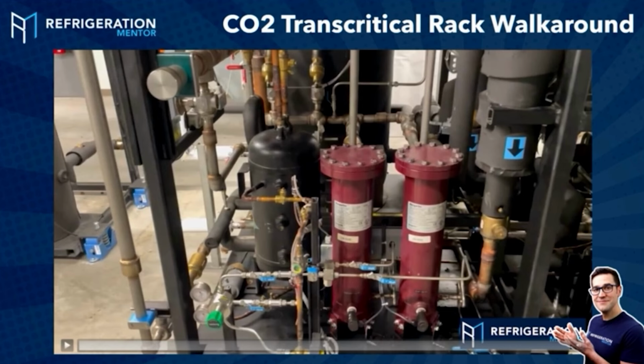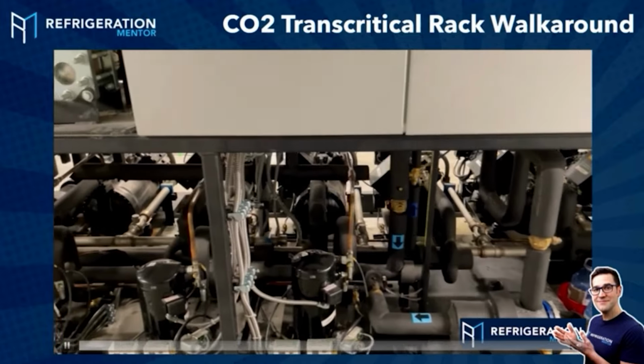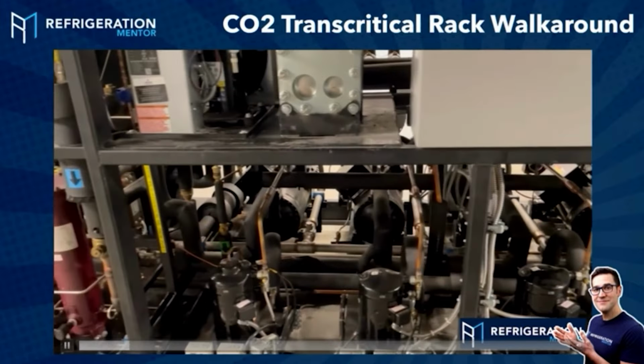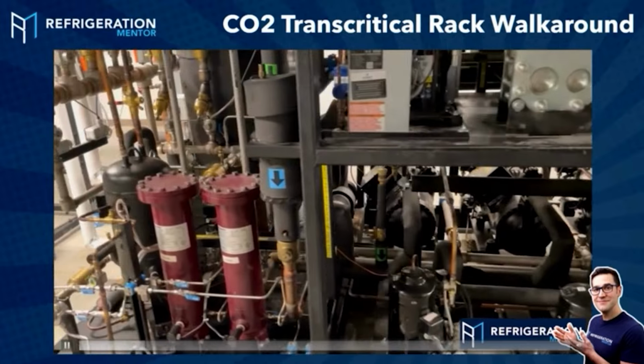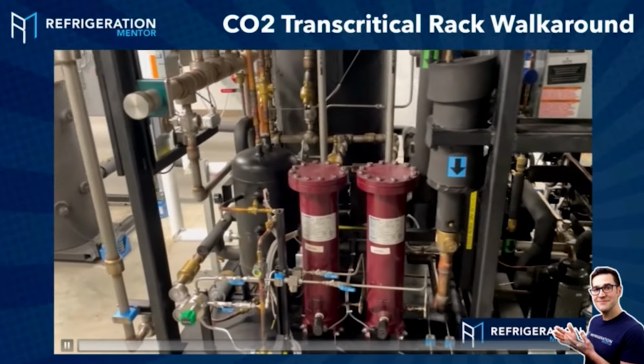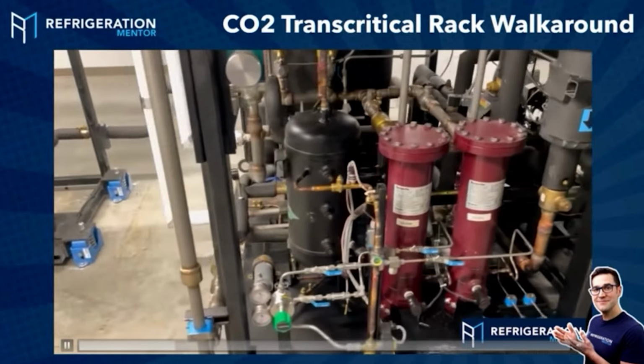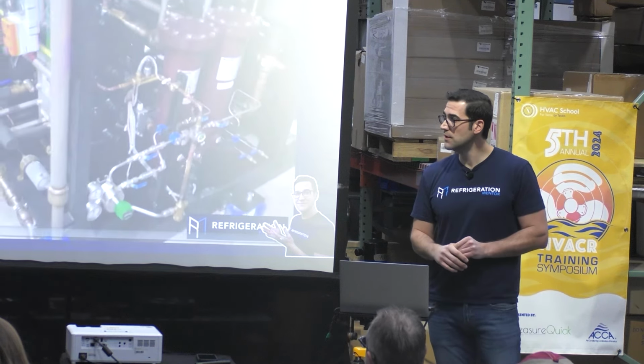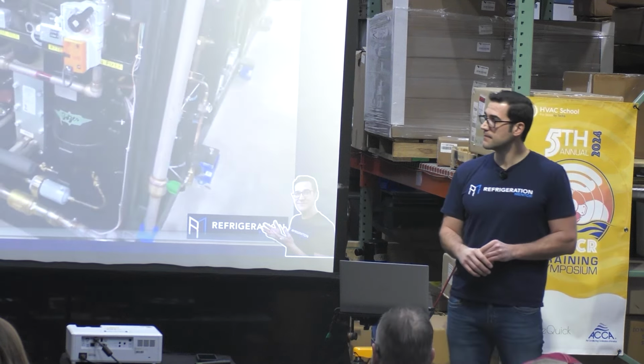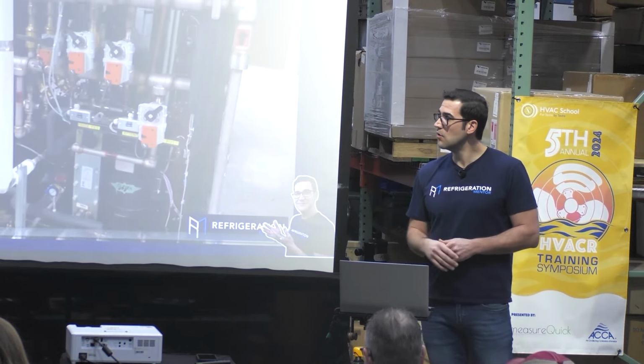So any of you that work in commercial HVAC and you have long runs, 300 or 400 feet, you'll have some sort of either oil management at the compressor itself or maybe even a system like this. In your residential systems, that oil is just being pushed through with the compressor. Maybe we'll walk through a little bit. So once again, here's the low temp compressors. We have an oil management system to make sure that oil stays in the system. You are going to have to learn about all those components as you go through. Then you have a vessel there that's an oil receiver.